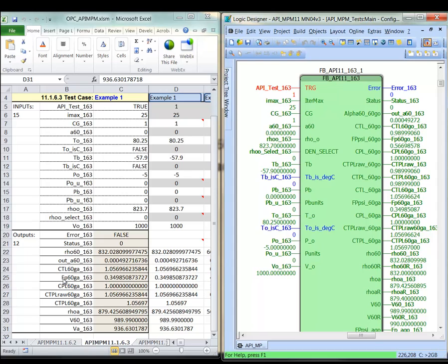And then we also have the scaled compressibility factor. We have the volume correction factor for pressure to go from alternate to 60 degrees base conditions. And then we have the combined CTPL. CTPL raw is used to correct densities, and CTPL is used to correct volumes.